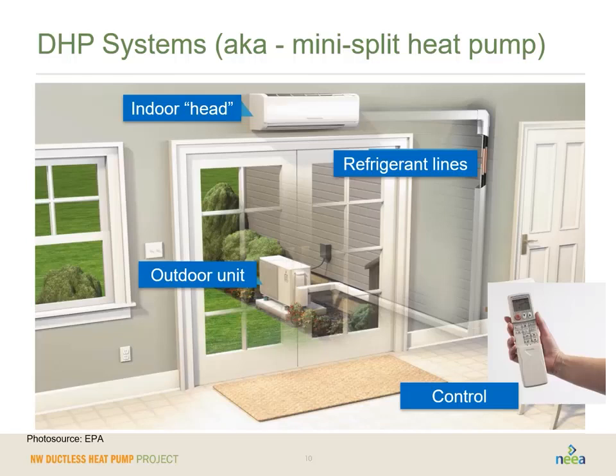Outdoors, we have the outdoor unit. It's also referred to as the compressor. Now with old heat pumps, this was a very large box that was very loud outside of your home. The modern outdoor units or compressors for ductless heat pumps are small. They're about the size of a suitcase, and they're much quieter. This is, again, both due to their size and due to that improved technology that I mentioned. They use what's called an inverter compressor, which allows it to be ramped up and ramped down quite smoothly as opposed to just on or off at a couple of stages. And because most homes, once they're heated or cooled initially, don't require the system to run at full steam all of the time, that's another reason why we can get these things to be more quiet and unassuming. It doesn't have to run at full speed most of the time. It's a smaller unit with more advanced technologies.